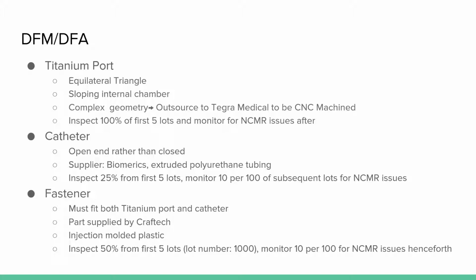engineering consideration. So for the titanium port, we decided on an equilateral triangle because it is a fairly simple shape, and the one point would allow it to be slid into place in insertion into the patient. We chose a sloping internal chamber so that it would be able to effectively deliver the drugs. And while it is a complex internal geometry, we decided to outsource to Tegra Medical in order to be CNC machined, which would be fairly easy for them to do. In order to validate that this met our specifications, we would inspect 100% of the first 5 lots and monitor subsequent lots for NCMR issues after.